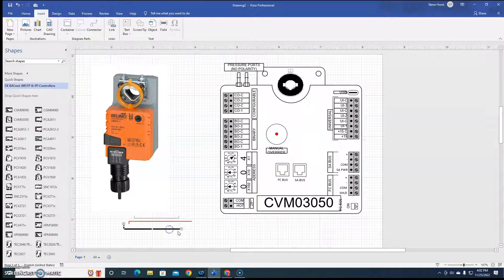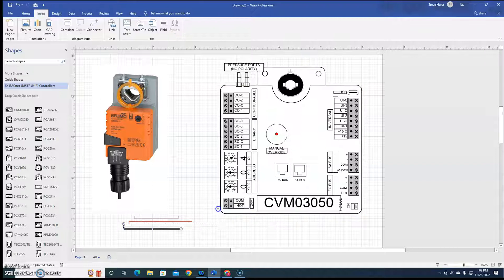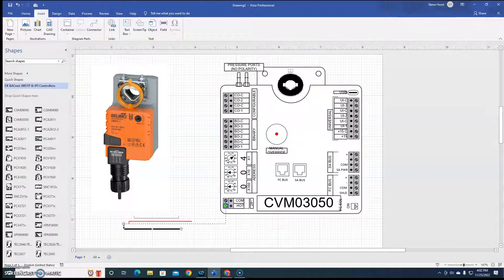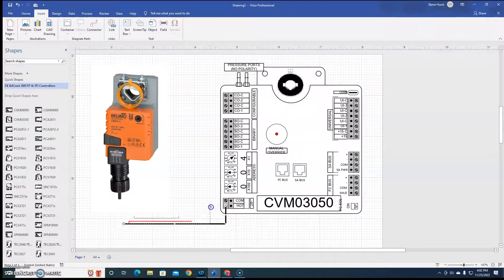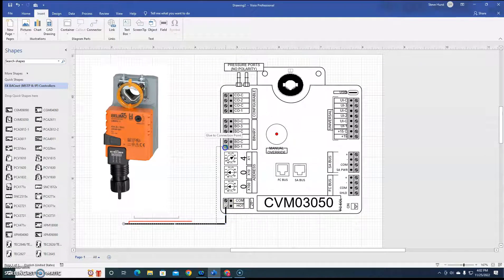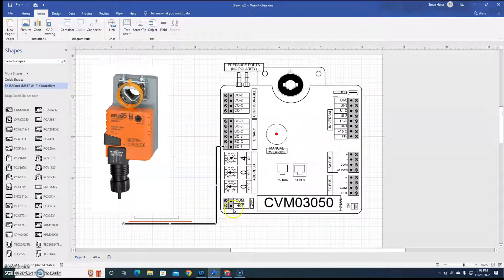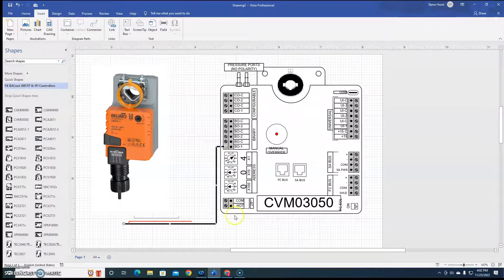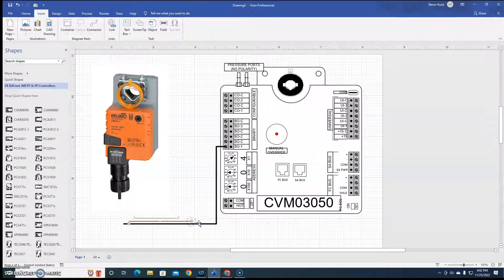First we're gonna take this black and you can do two options here. We can go and hook it up to hot on our controller like that and that'll work, or we can hook it up to BO1. I'm gonna hook it up to BO1 because we already know we got a wire coming in on hot. So I try to avoid putting two wires in a terminal if I can.